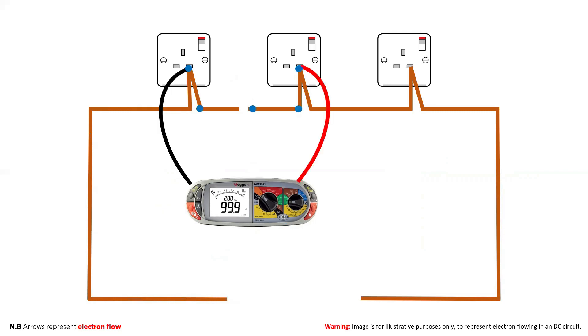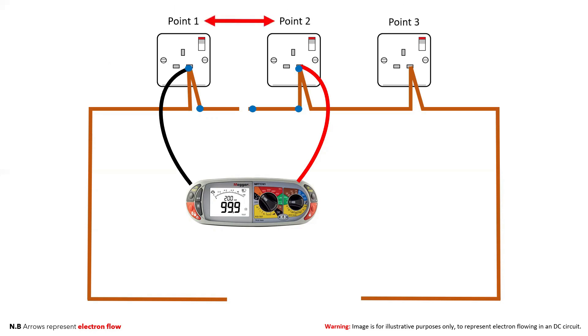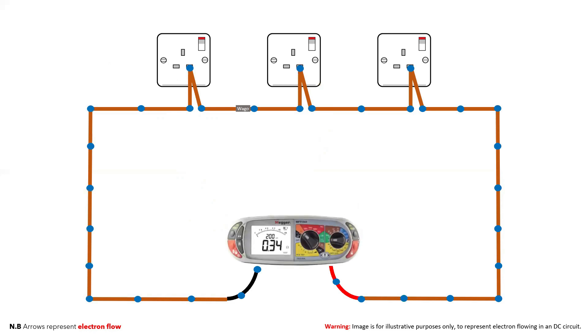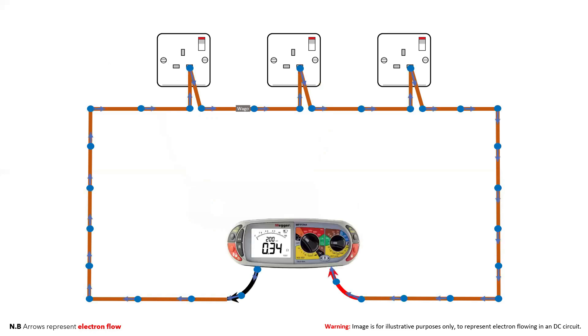If your low ohm resistance tester is not registering a reading, then there must be a break in the cable. If there is an open circuit, the electrons cannot flow and the meter has nothing to measure. If we label these points one, two and three, then the fault would be between points one and two. Repair the fault with a Wago box or similar using maintenance free connections if it is not easily accessible. Make sure that you retest the repaired circuit to prove that the repair has worked.